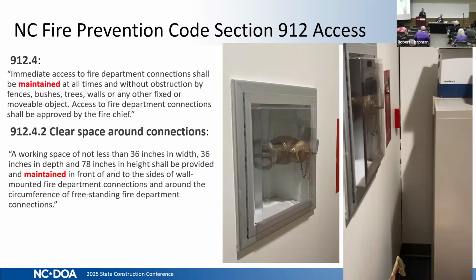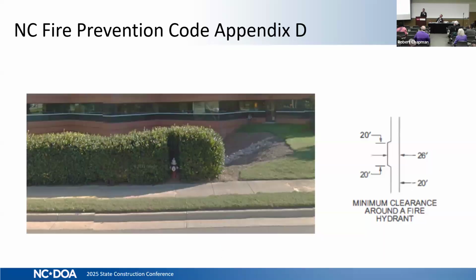All right. And kind of along those same lines, North Carolina Fire Prevention Code Appendix D. And here you see some required clearances, 20 feet on each side of that hydrant. They did a great job camouflaging this. I think maybe green paint would have made it complete. But the thing is that the state construction office can't police this, because even though they're the authority having jurisdiction, they can say something, but they can't enforce it unless the local fire jurisdiction has adopted Appendix D of the North Carolina Fire Code. So that might change as we go throughout the state. This might be something that can be enforced, or it may not be. But at the very least, we could recommend to the facility that, hey, look what Appendix D says.